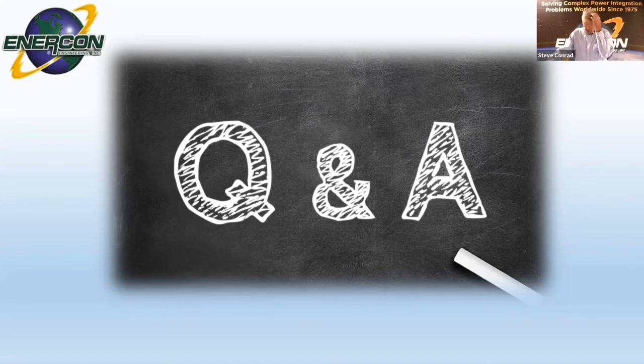That's a good question too, especially if you have existing generators that parallel with existing utilities - usually that's not going to require breaker ratings to change. But we've done systems where a customer had existing generators that presently don't parallel with the utility, and then all of a sudden they rewrite the contract with the utility to allow them to peak shave. Right then and there - and a lot of people tend to forget this - once you parallel with the utility, fault current availability can increase, so you definitely have to be aware of that.